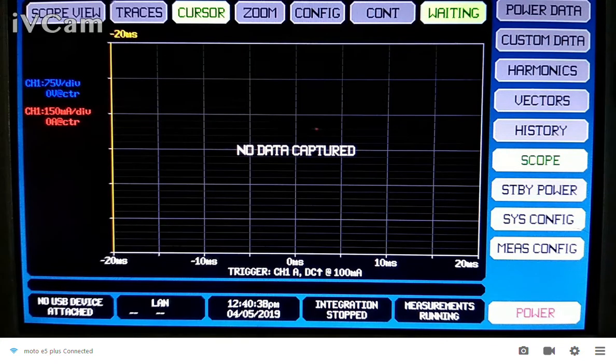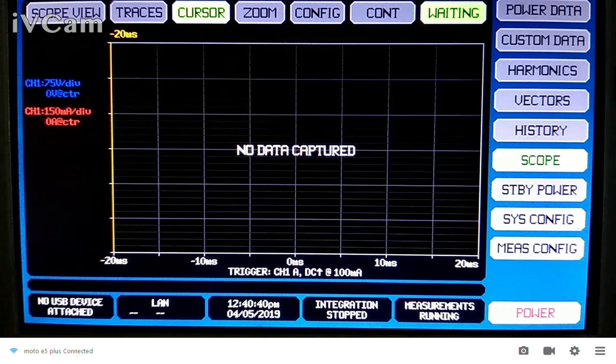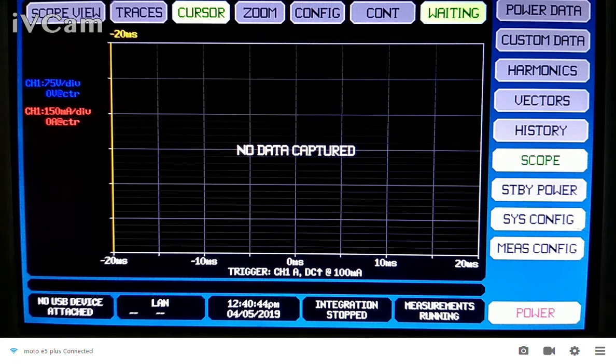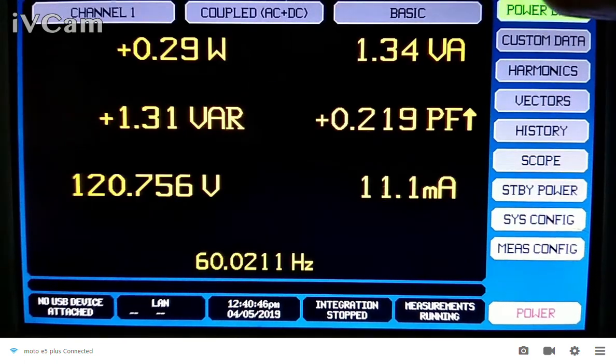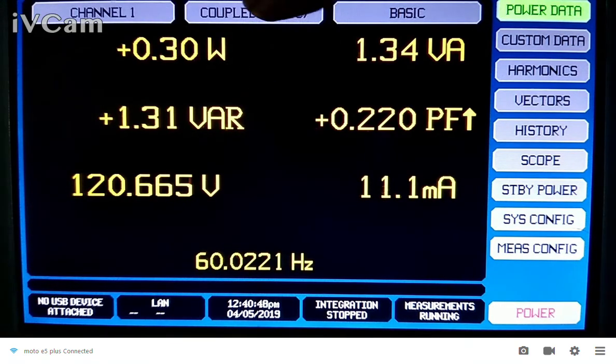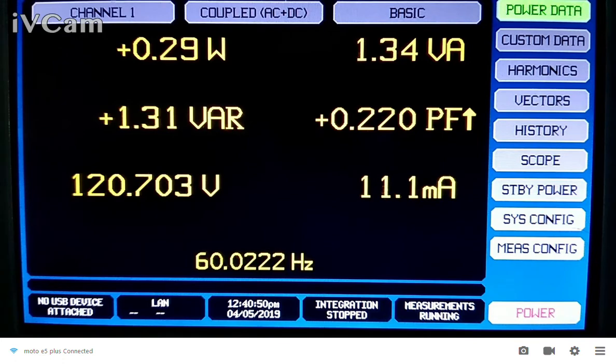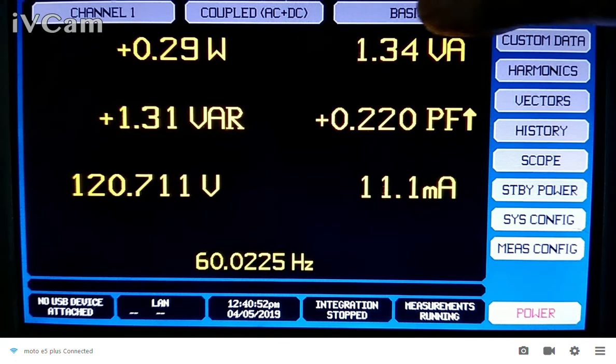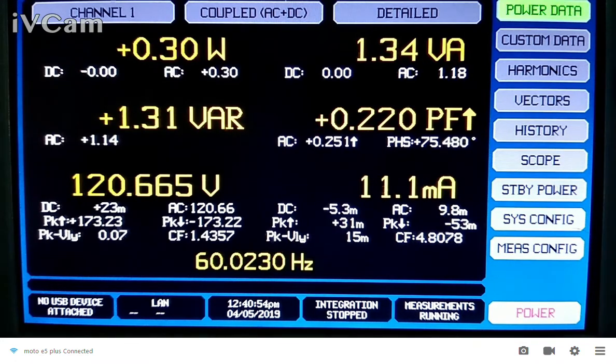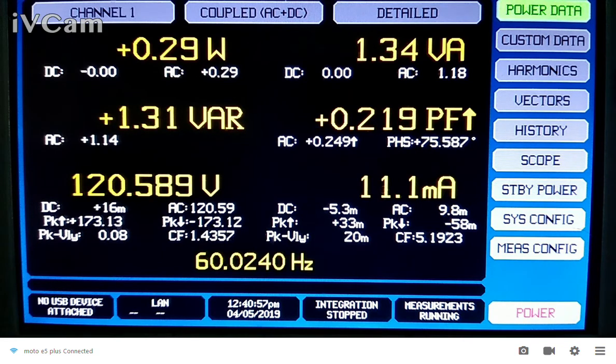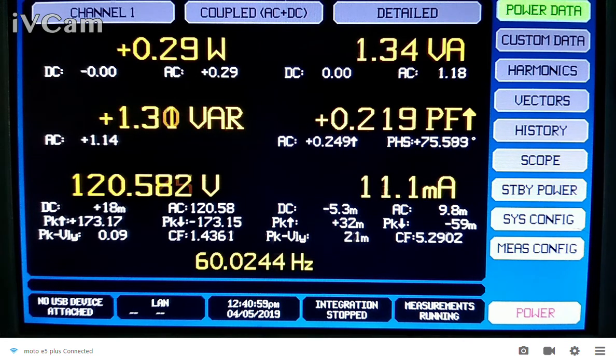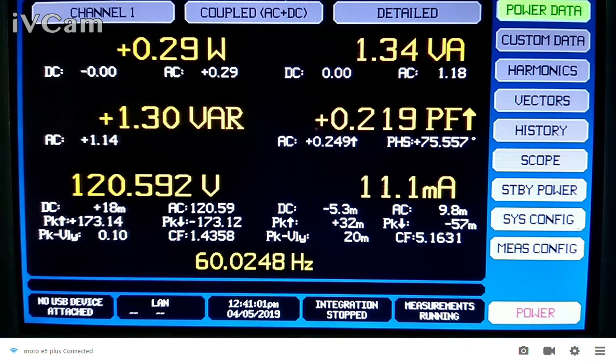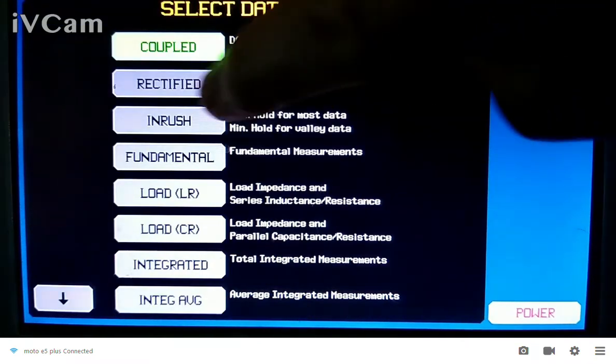Now what I'm going to do, in addition to the oscilloscope, there's also another mode specifically for inrush current. The way you do that is you just hit this power data, and then this is the normal mode. I can turn on more detail if I want. This starts giving me a breakdown by AC and DC and the various different peaks if you want more detail. But the one I'm going to look for is called inrush.